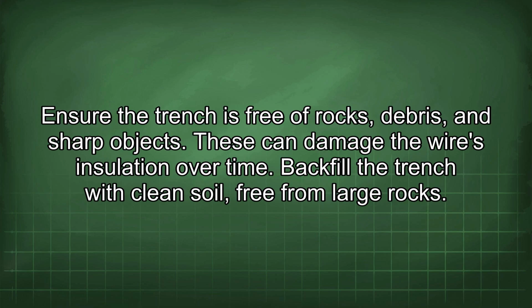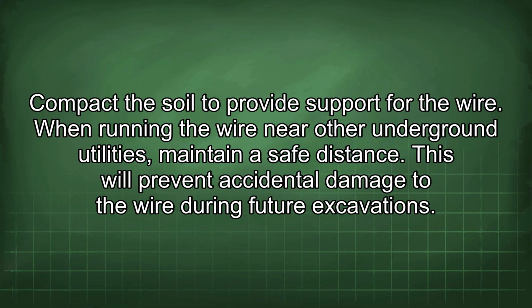Ensure the trench is free of rocks, debris, and sharp objects. These can damage the wire's insulation over time. Backfill the trench with clean soil, free from large rocks. Compact the soil to provide support for the wire. When running the wire near other underground utilities, maintain a safe distance. This will prevent accidental damage to the wire during future excavations.